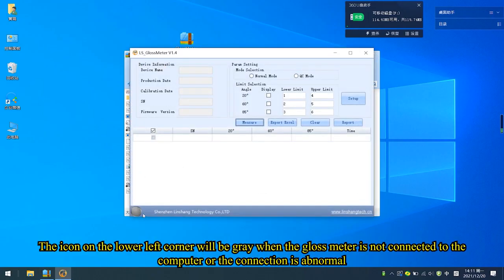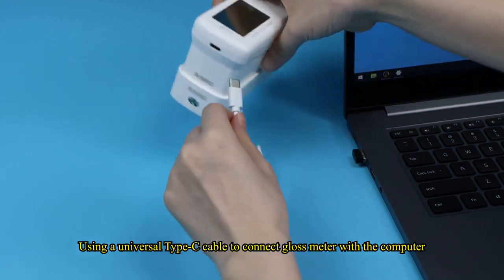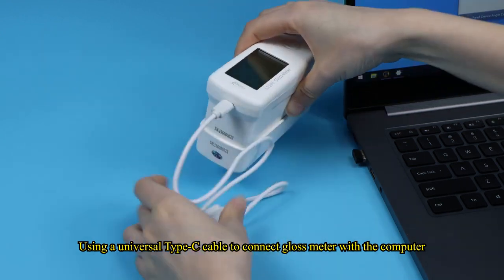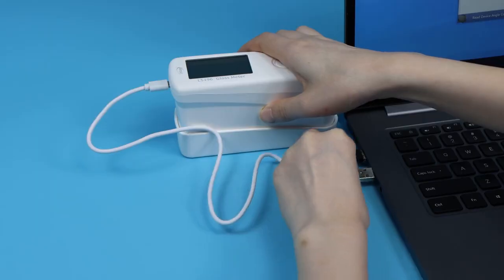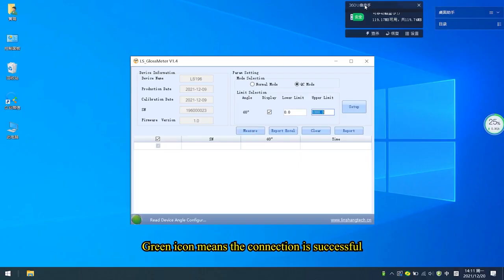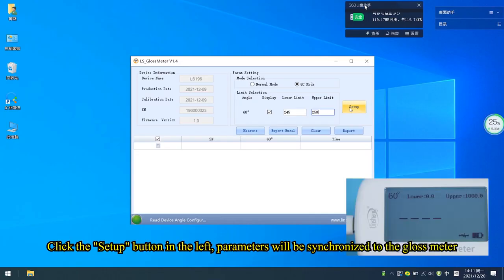The icon on the lower left corner will be gray when the gloss meter is not connected to the computer or the connection is abnormal. Using a universal Type-C cable to connect the gloss meter with the computer. Green icon means the connection is successful. Here you can set the upper and lower limits in QC mode. Click the Setup button on the left. Parameters will be synchronized to the gloss meter.